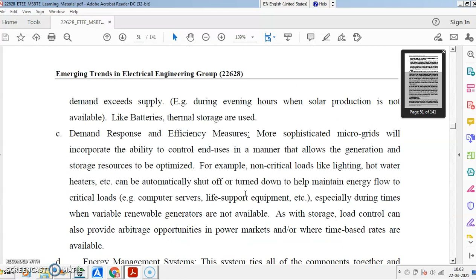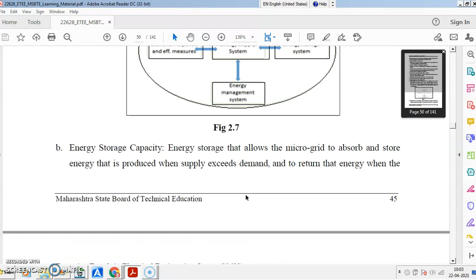Then utility grid interconnection. So, the energy management system. This system ties all the components together and maintains real-time balance of generation and load. You have to always maintain this balance of load and demand. In a very simple case, the microgrid control system is typically a governor control on a diesel generator. In a more complex microgrid, control systems are made up of sophisticated software platforms with sensors, metering and communication devices, designed for real-time optimization and control of the generator, energy storage, loads, utility interchange, etc.